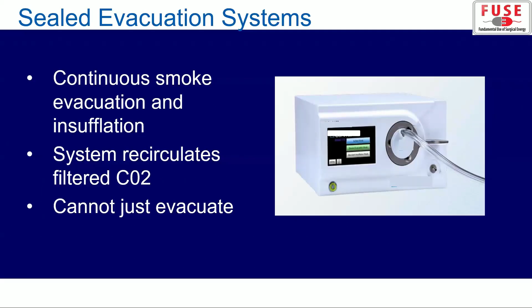And then there's sealed evacuation systems. Basically, there's continuous smoke evacuation and insufflation. So the CO2 kind of circulates and recirculates through this filter and this machine into the abdomen and out of the abdomen. So this filters as it's insufflating, so it's easy to maintain pressures when you're doing laparoscopic surgery. Problem is you can't just evacuate it, it circulates. So at the very end, when you have to release the pneumoperitoneum, you do have to open your port, which means that if there's surgical smoke still in there, that's going to affect the surrounding air. And so what you want to do is wait until it circulates a couple of times, and all the air in the abdomen has been filtered out. Then you release the pneumoperitoneum. Next slide, please.